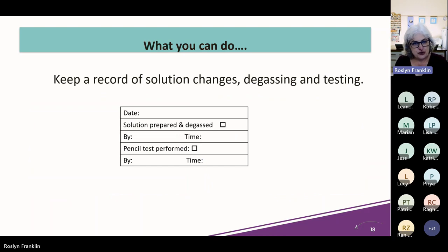The other most important thing is, once you've done this test, you need to record it. Please record it. If I'm auditing your practice, that is one thing I'm going to be looking at - your sterilization records, because that's how I can track that an instrument has been through your process, and track the process it's been on.